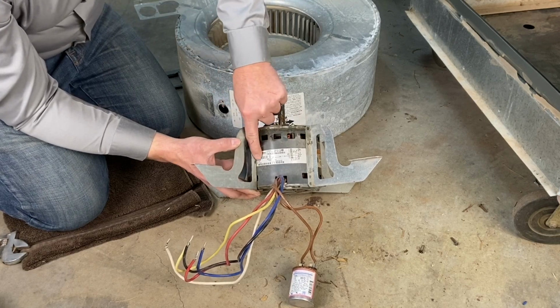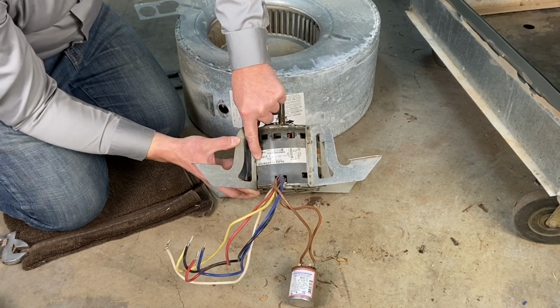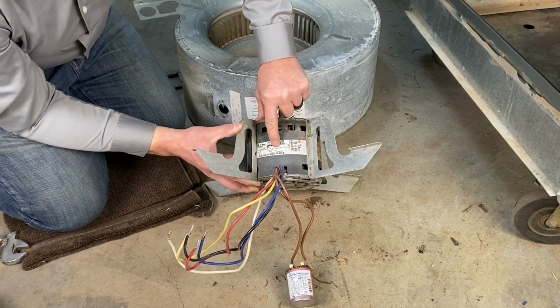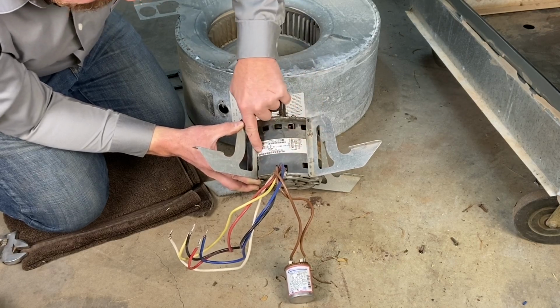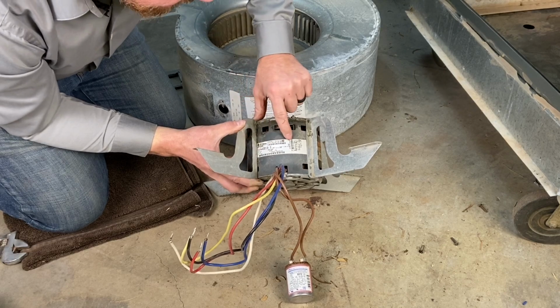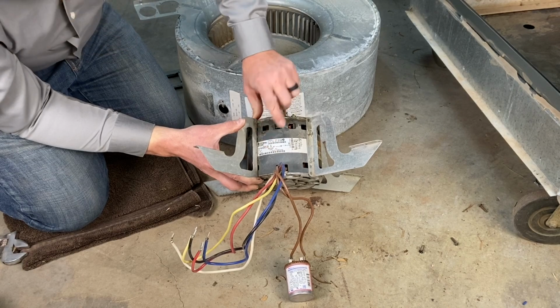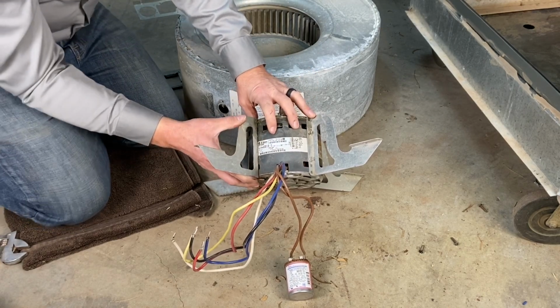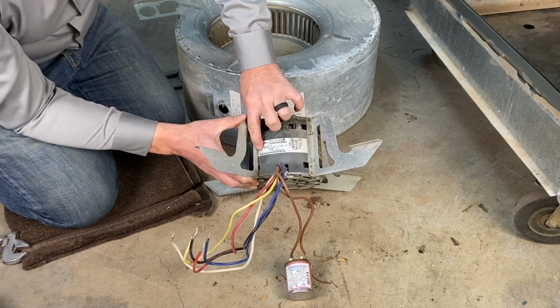If I was going to replace this motor, the information I'm going to need is right here in the tag. This is a 1/2 horsepower, 115 volt motor. We also need the RPM of this motor, and it's on here somewhere. Oh, here's the amps, 7.1 amps, and the RPM being 1,000 RPMs, rotations per minute. So when I go to get the new motor, I don't need to take this motor with me and dump it on the counter. I need to get 1/2 horsepower, 115 volts, 7.1 amps, and RPMs being 1,000 RPMs.